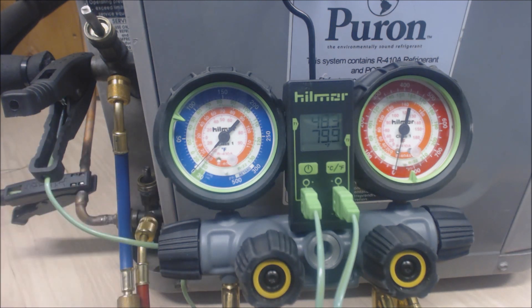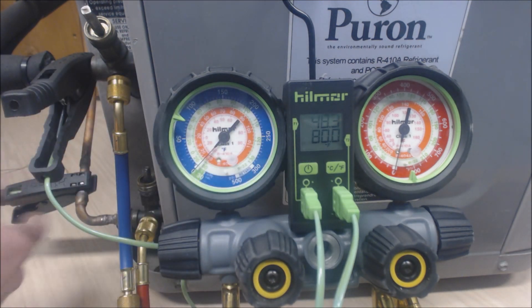Hey guys, this is AC CyberSpec and today we're looking at checking the refrigerant charge on an R410A heat pump. It says Puron, and the heat pump in cooling mode is looking for 14 degrees of TXV subcooling. We're checking it with the hilmor four-valve aluminum gauge set, which has remote clamp-on style temperature sensors.